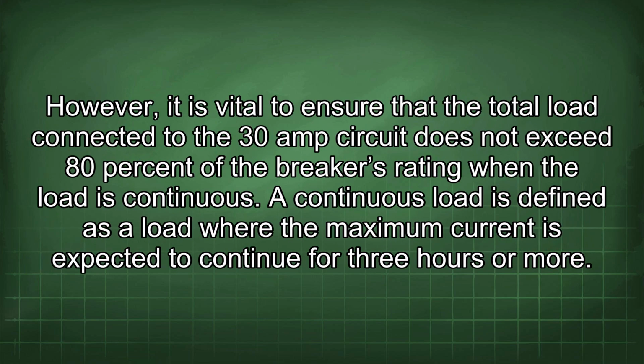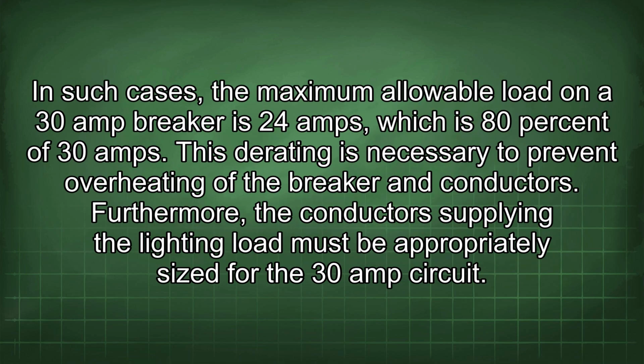However, it is vital to ensure that the total load connected to the 30 amp circuit does not exceed 80% of the breaker's rating when the load is continuous. A continuous load is defined as a load where the maximum current is expected to continue for 3 hours or more. In such cases, the maximum allowable load on a 30 amp breaker is 24 amps, which is 80% of 30 amps. This derating is necessary to prevent overheating of the breaker and conductors.